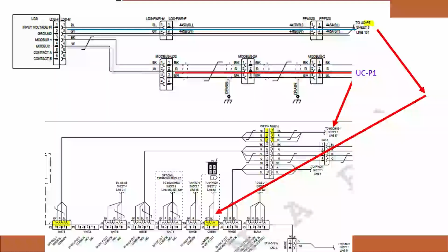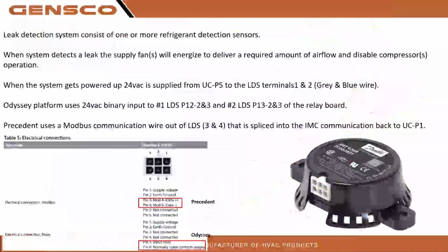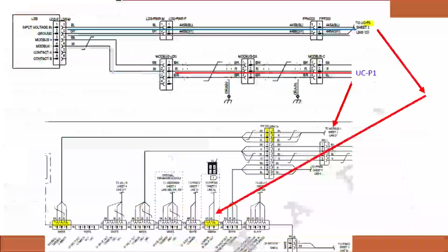Here's a quick overview of the Precedent rooftop unit Modbus. Here's our leak detection. That's our sensor right there. A lot going on there. So it's going to be communicating to UCP1, and that's the top of the Symbio board. So that is our 24 volt going to it. Now be aware, this sensor is normally open until energized. If we try to see if that thing's closed, because it's supposed to be normally closed during normal operation, and it's going to open when it senses refrigerant, it is normally open until we apply power. Keep that in mind.